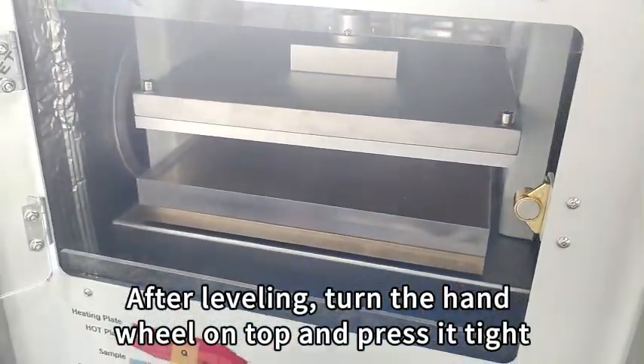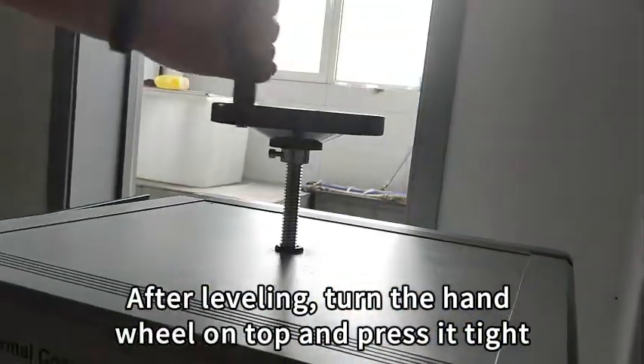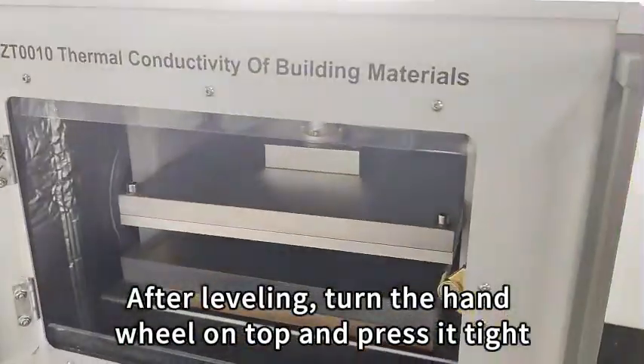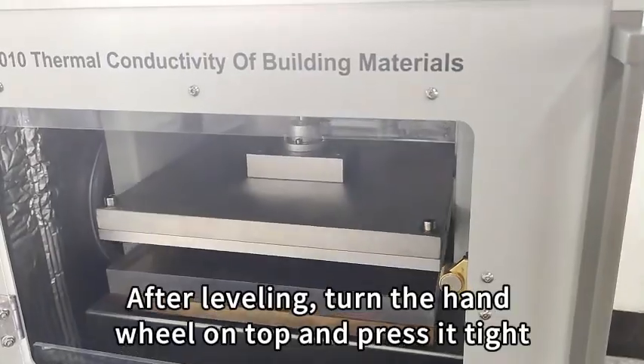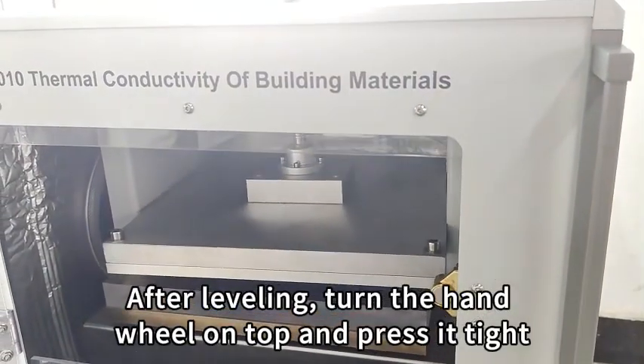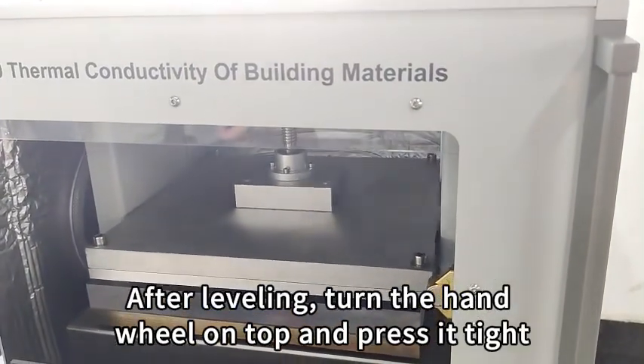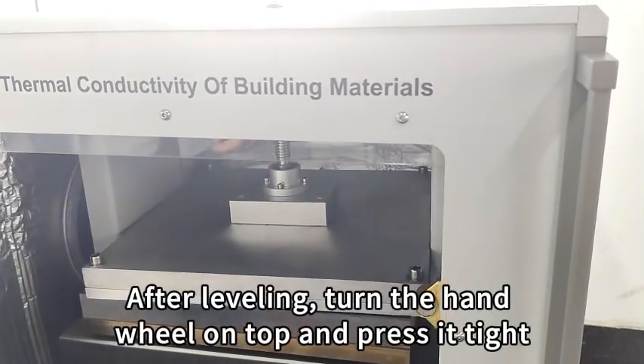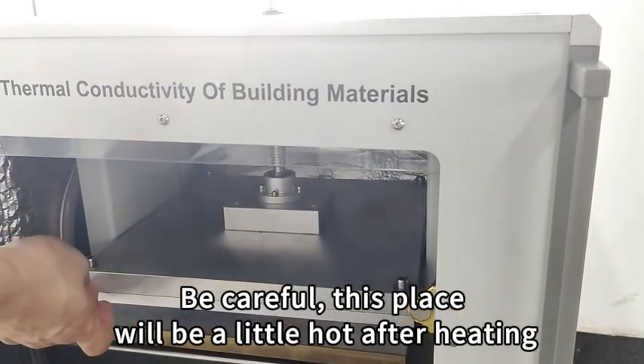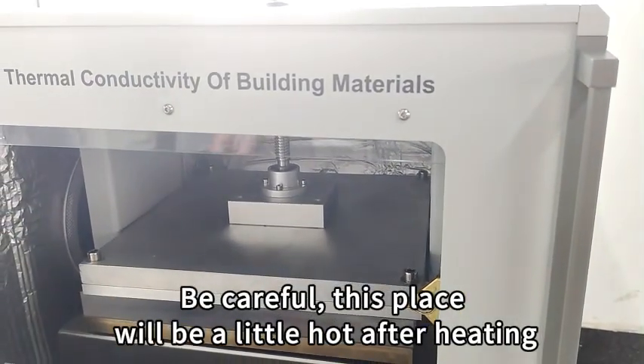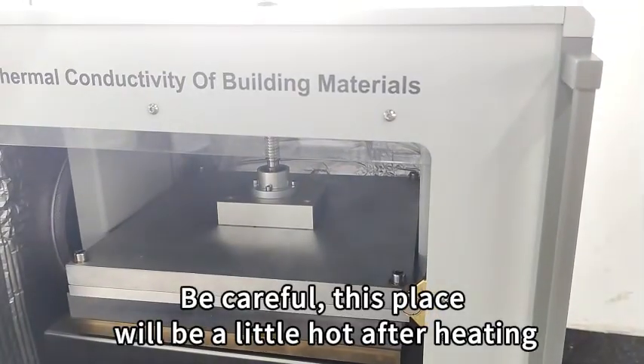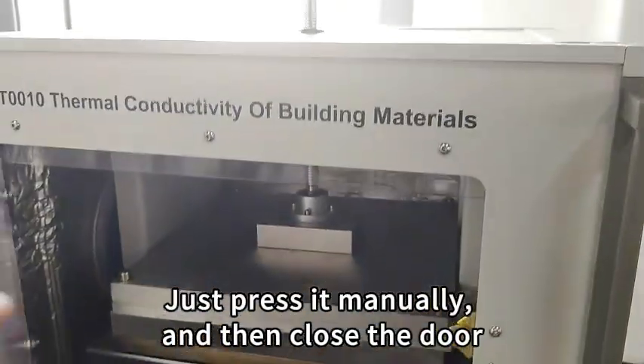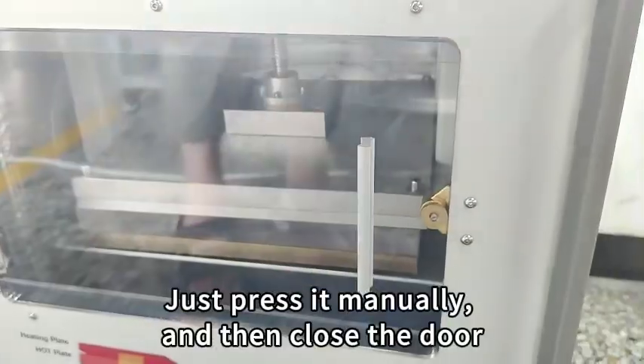After leveling, turn the hand wheel on top and press it tight. Be careful, this place will be a little hot after heating. Just press it manually and then close the door.